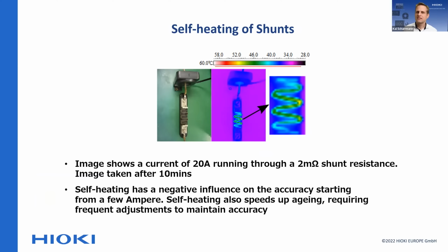And in this case, in the picture, you can see the shunt. This is a 2 milliohm shunt. There's 20 amps of current being driven over it, and this image is taken after about 10 minutes. Originally, the temperature was of course much lower than it was after 10 minutes. So the temperature increased by about 20, 25 degrees from room temperature to around 50 degrees at the shunt.